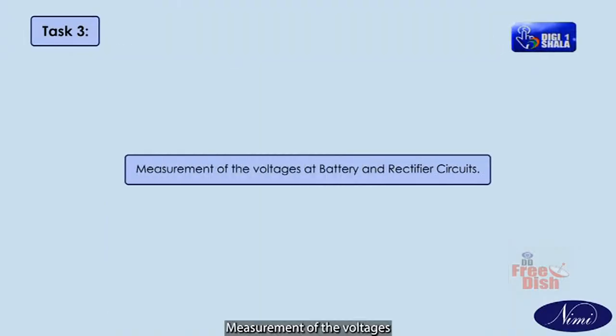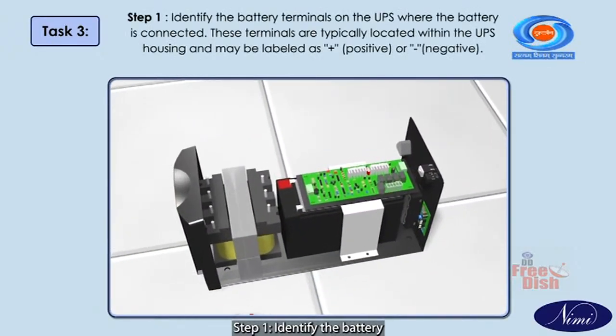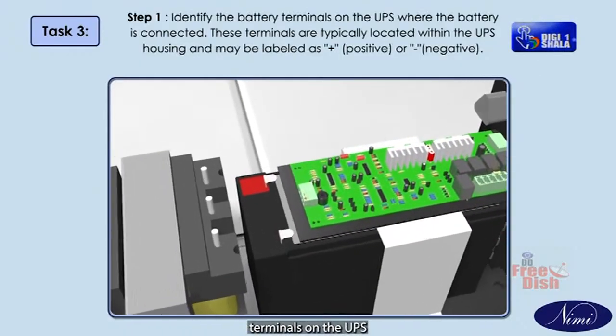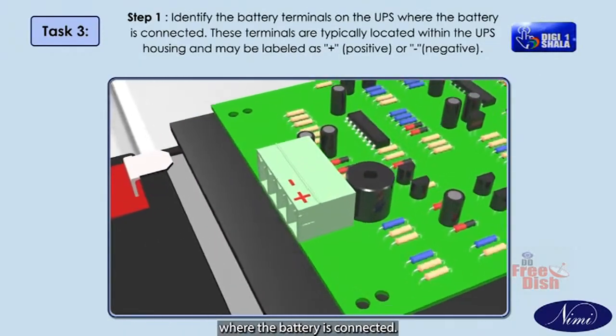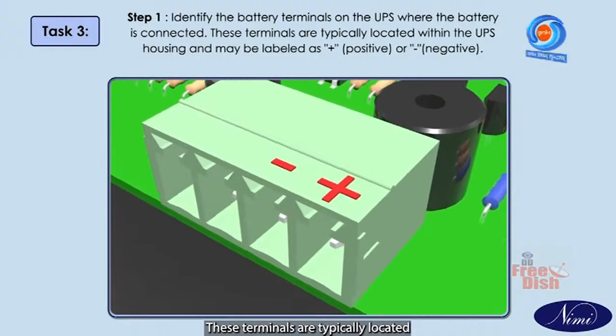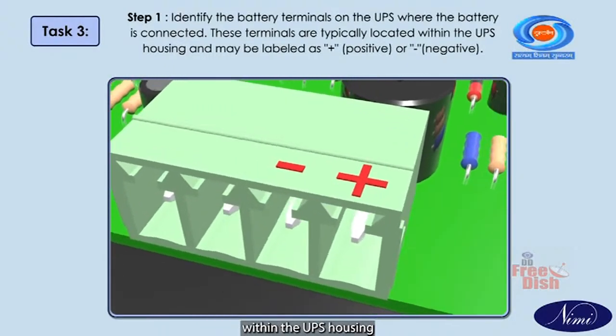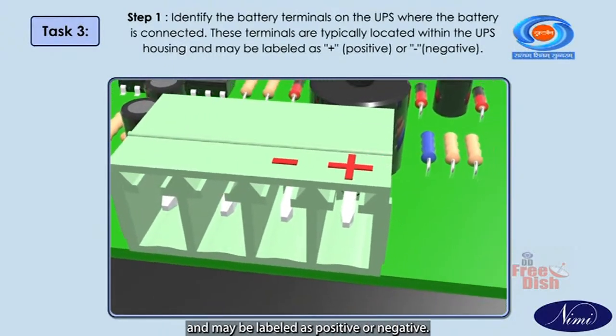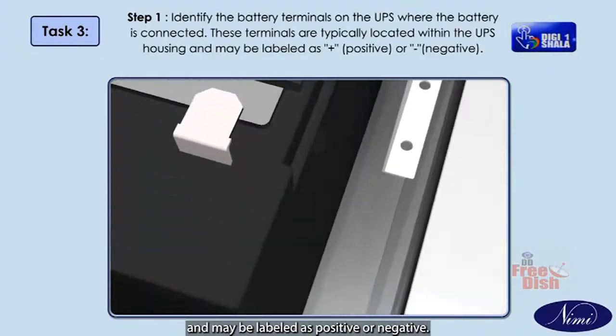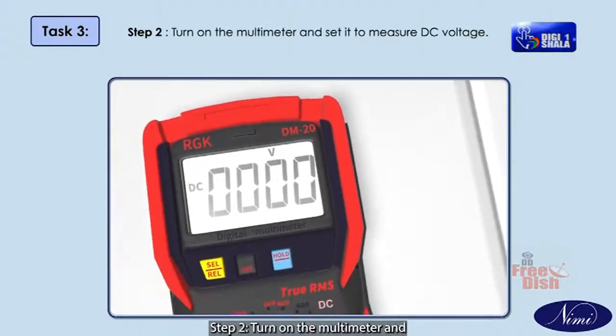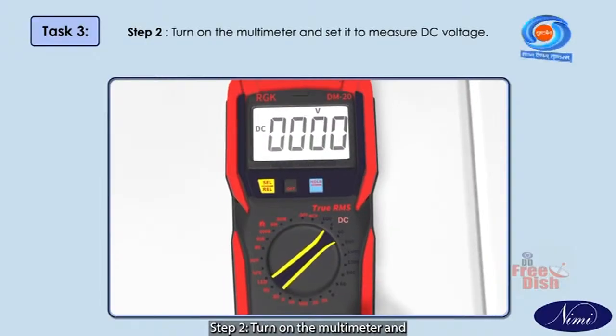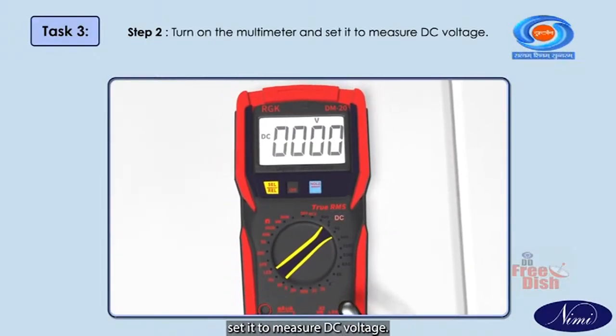Task 3. Measurement of the voltages at battery and rectifier circuits. Step 1. Identify the battery terminals on the UPS where the battery is connected. These terminals are typically located within the UPS housing and may be labeled as positive or negative. Step 2. Turn on the multimeter and set it to measure DC voltage.